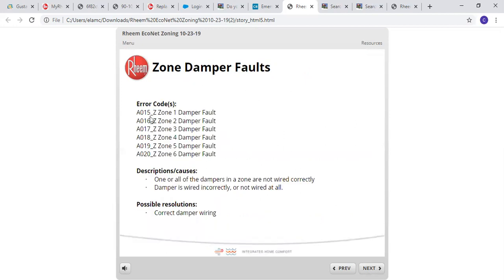Some other damper faults here, zone 1 through 6. We'll pick A017Z, zone 3 damper fault. Some possible causes: one or all the dampers in a zone are not wired correctly. One could be a damper is wired incorrectly or not wired at all. We had one where that was the case. For whatever reason, it was wired on the board, but it wasn't wired at the one damper, and this is the fault they got. So possible resolutions: correct damper wiring.